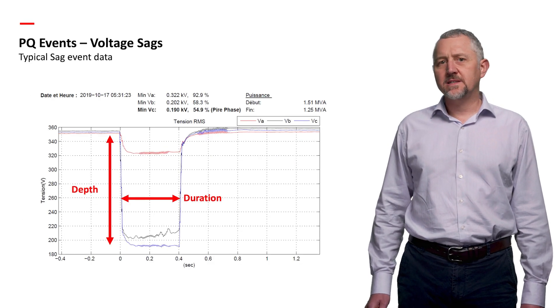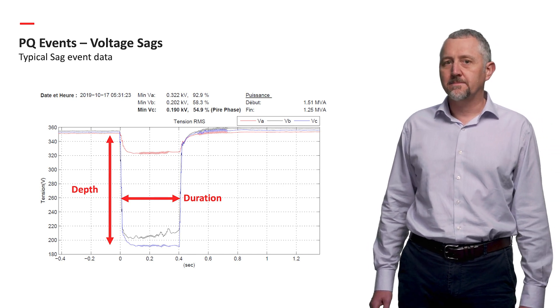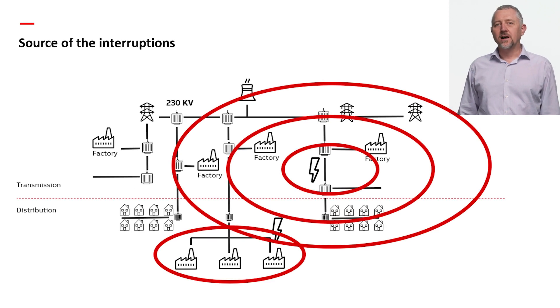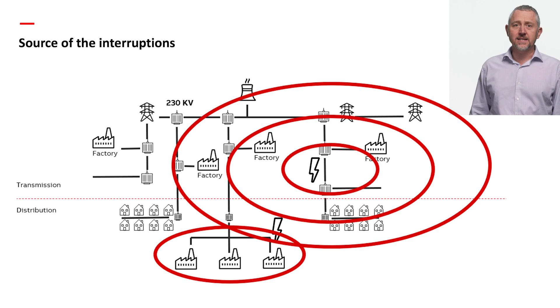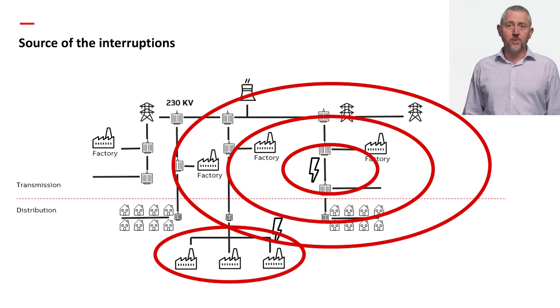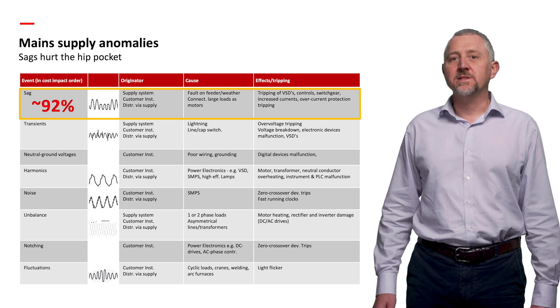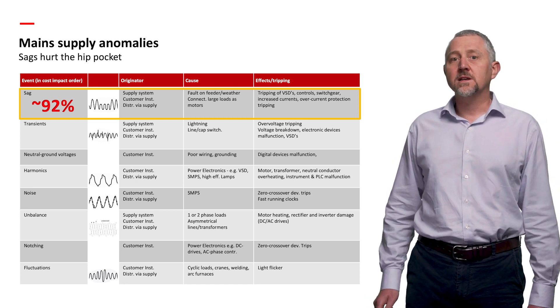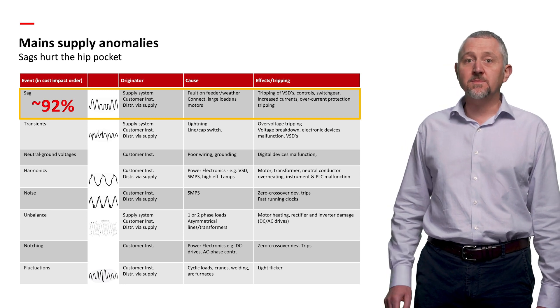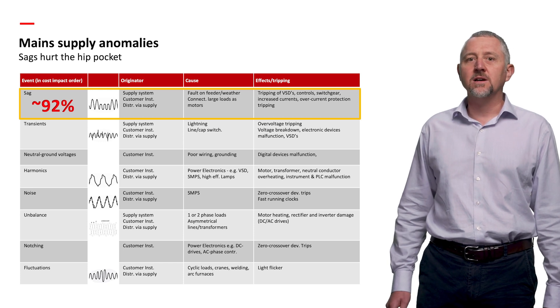Voltage sags are defined by their depth and duration, and understanding these values is essential for selecting the appropriate solution. Faults in the transmission network are the most disruptive. As industries become more automated, the sensitivity to power quality events increases. Even short events can lead to unexpected stops in processes, resulting in product damage, wastage and production shortages. sags represent approximately 92% of all power quality issues. Faults, large loads, supply system problems, customer installation and distribution issues can all contribute to their overall impact on business operations.